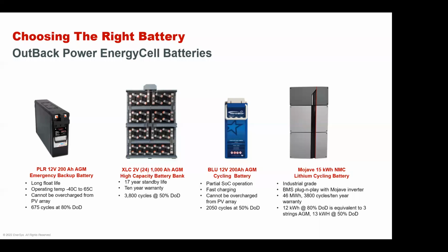Okay, so choosing the right battery. If you can use an AGM battery, this is kind of our current offering. These are UL 1989 listed. The pure lead battery has a long float life. It's got a great operating temperature range. It cannot be overcharged from the PV array. This is unique. Most lithium batteries and even a lot of AGM batteries, even our high capacity batteries, have a maximum charging current that needs to be followed. With our PLR battery and our BLU, the blue battery over here, that's not a problem. They cannot be overcharged from the PV array.